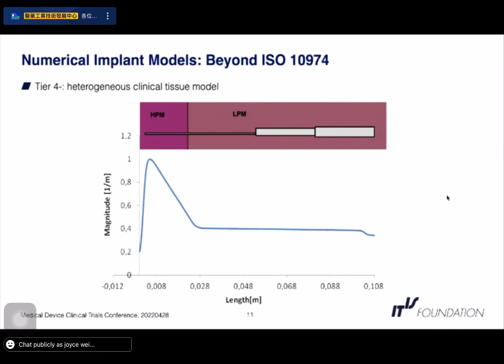Other things that need to be considered and everybody needs to be aware of that go beyond the implant safety standard 10974 is that increased heating or power deposition can be caused by damaged, broken, or abandoned implants within the human body. If we have multiple leads that are very close together, there can be a proximity enhancement effect. And also the voltage response that cannot only be part of the damaging of the IPG to an extent that it deposits more power or that it damages the implant so that it doesn't work properly anymore.